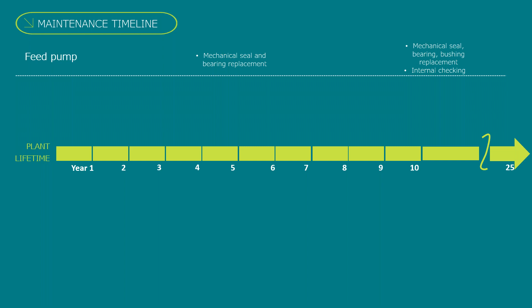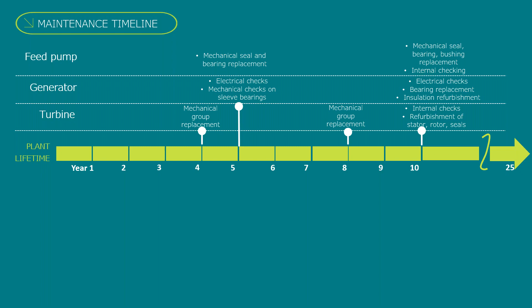The same, more or less, is for the generator, which doesn't need much maintenance, and the big refurbishment is only after 10 years, with the check of the electrical windings and replacement of bearings, sleeve bearings. Then we have the turbine, where the wear parts are concentrated in the mechanical group, which is the core for the transmission of torque through the shaft. And we have seen that the blades are not impacted. So the opening of the turbine is only suggested after 10 years for the check of the internals. Then about the mechanical group, we are going to see soon an insight about this replacement activity.